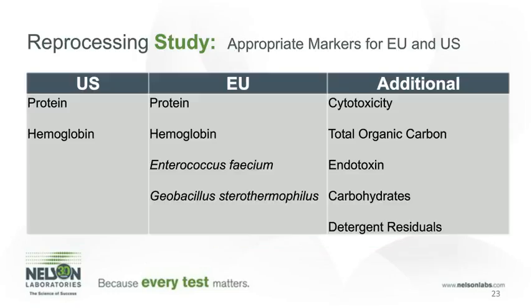After visual inspection takes place, the device is then extracted and tested for specific residuals. The types of residuals depend on the surgical procedure itself and also where the device will be sold. The U.S. FDA requires two quantitative methods of testing, and the most popular methods of testing right now are protein and hemoglobin testing. In Europe, specifically for the CE mark, Geobacillus stearothermophilus spores are specified as necessary to test for medical devices. If the devices are going to be sold or utilized in Germany, and specifically the Bavarian government, Enterococcus faecium needs to be performed as well, the bioload reduction.